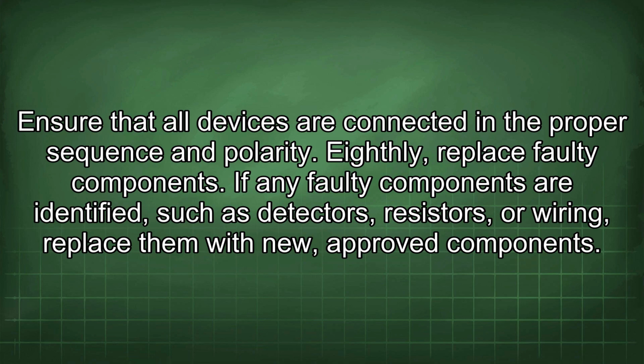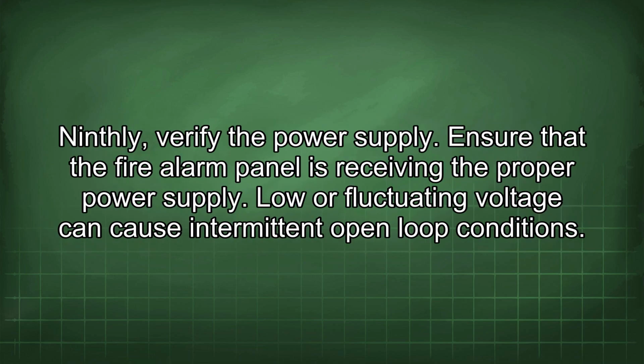approved components. Ninthly, verify the power supply. Ensure that the fire alarm panel is receiving the proper power supply. Low or fluctuating voltage can cause intermittent open loop conditions.